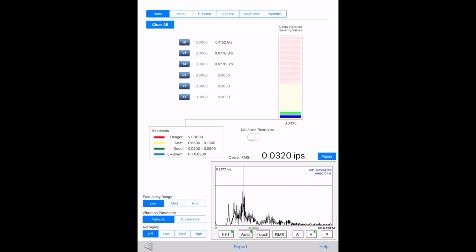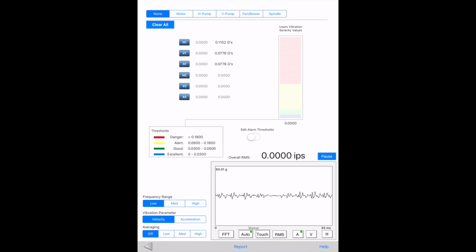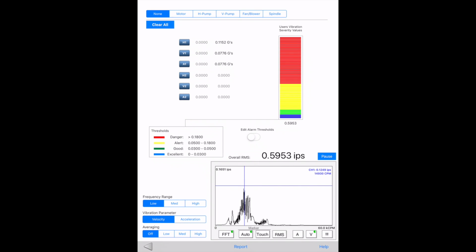The bottom part of this page consists of a real-time signal viewer. It continuously updates vibration signal in time waveform or FFT spectrum. Acceleration signal from the accelerometer is used directly for analysis or integrated to velocity. You can use 2 fingers pinch to zoom to a specific frequency range, or quickly use the selector on the side to change frequency range.